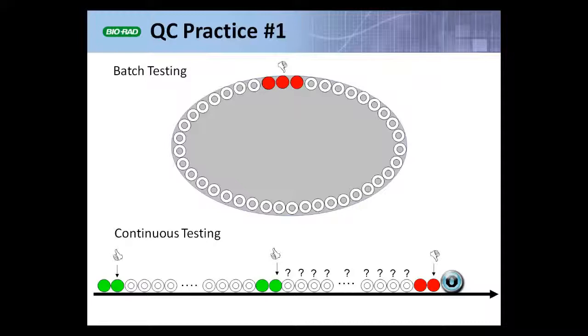I need to test those QCs after the last patient result but before the end of the day or calibration event. If I get a QC rule rejection, I have to acknowledge that there's a good chance something went wrong adversely affecting those patient results since the last good QC event, and I need to correct those results.